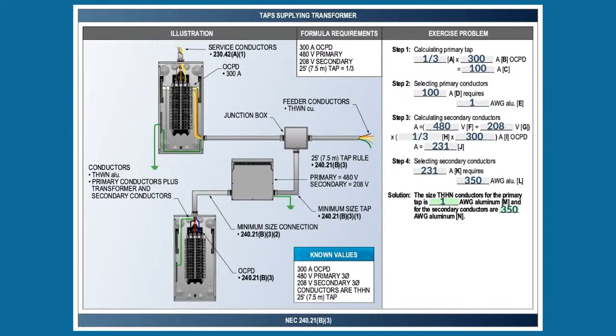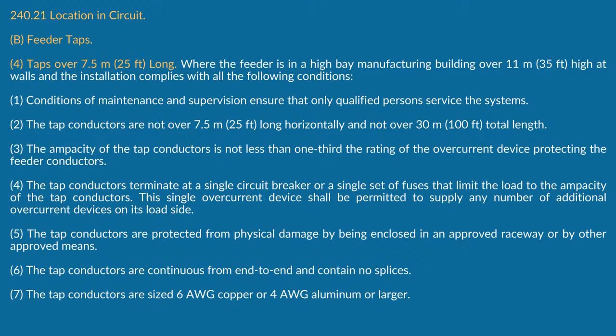But the main point is, since we're sizing the tap, let's see what it says here. I'm sorry, I didn't mean to touch that. If I look at this, it tells you in B43, it says the ampacity of the tap conductors is not less than what? A third. Looky there, I didn't change anything. So far, my rule of thumb is holding up. All right. Yeah. I haven't seen a rule of thumb come from you that didn't work.